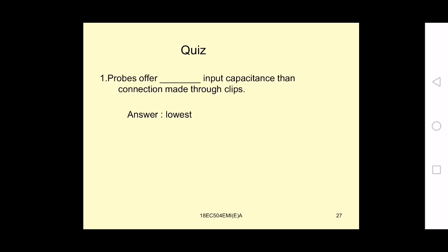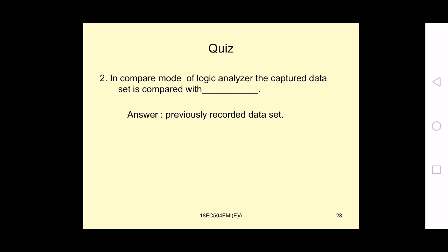Probes offer the lowest input capacitance compared to connection made through the clips. In compare mode of the logic analyzer, the captured data set is compared with a previously recorded data set.